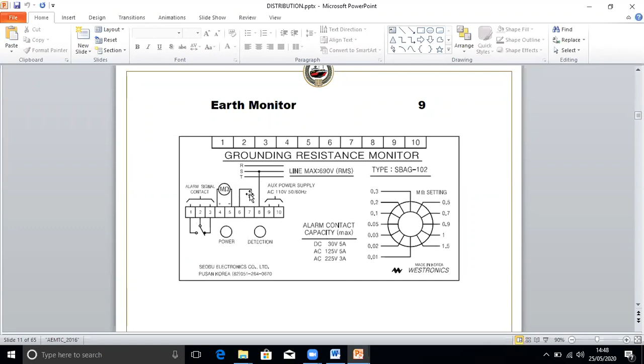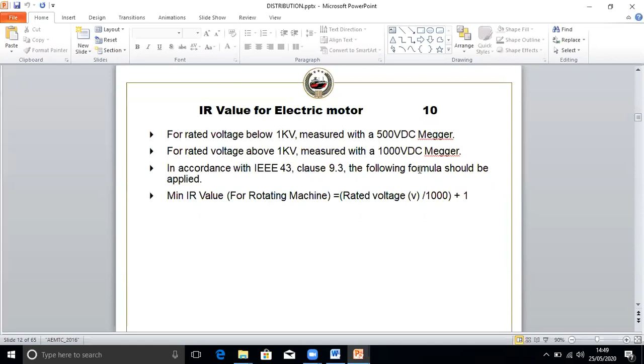So normally for rated voltage below 1 kV, that is below 1000 volt, we call it low voltage. You can use a 500 volt mega. But if it is more than that, then you have to use higher voltage megas. So like 6,600 volt, you have to use a 5000 volt mega. Below 1 kV, that means below 1000 volt, you can use a 500 volt mega.